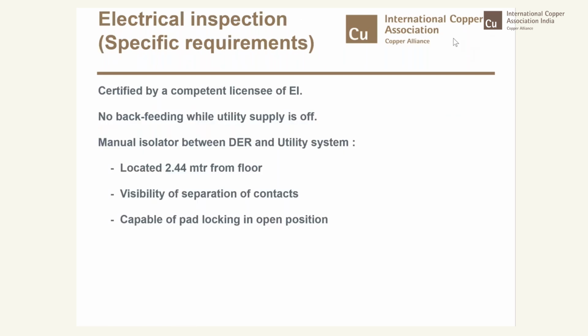And of course, I think I've mentioned all this in the electrical inspectorate requirements. Minimum is that the installation has to be certified by a competent licensee of appropriate licensee class, and you need to ensure that there is no backfeeding while the utility supply is off, which means anti-islanding. Additionally, you need to provide a manual isolator between the distributed source as well as the utility system, which has to be operated by the utility personnel, located 2.44 meters from the floor, with visibility of separation of contacts, and capable of padlocking in open position. These are the absolute requirements of that isolator.